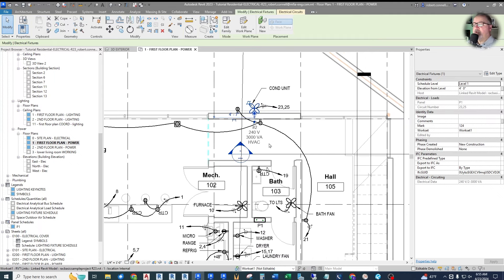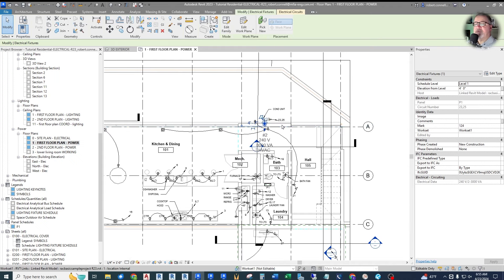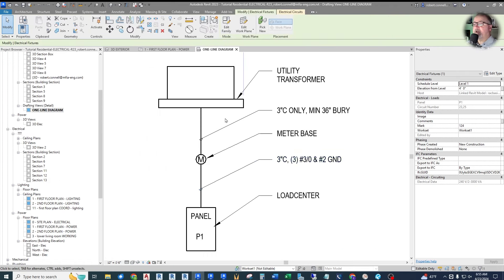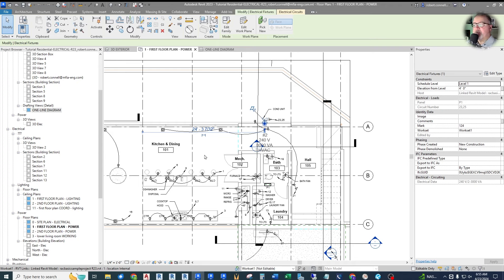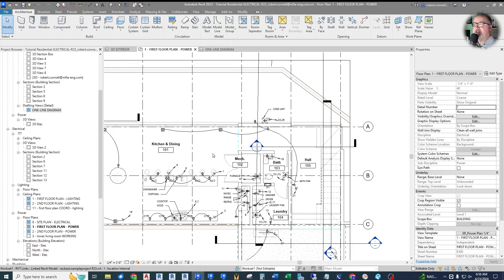In Revit you could just create a schedule with a drafting view like we did our single line diagram, and some people do that first — it's a fairly quick method. You can just draw some lines and put in all the values. But to truly use Revit's built-in database-driven model where things are centrally stored and can be shown in different places, I want to show how we can create a mechanical equipment schedule using the data contained within your model.